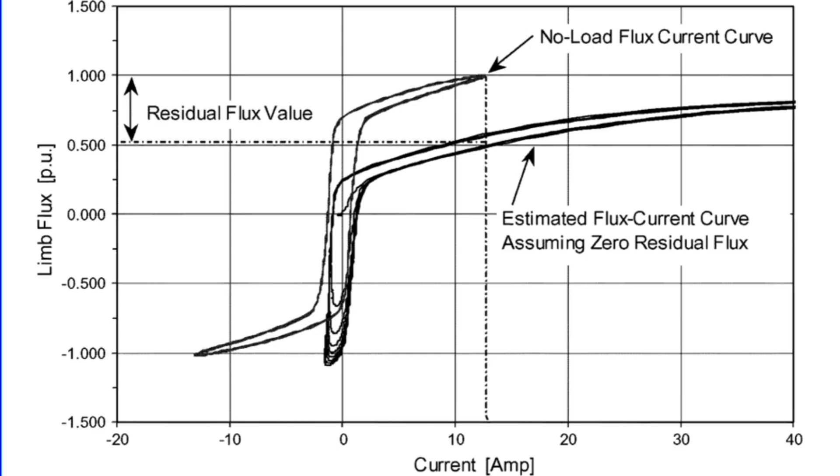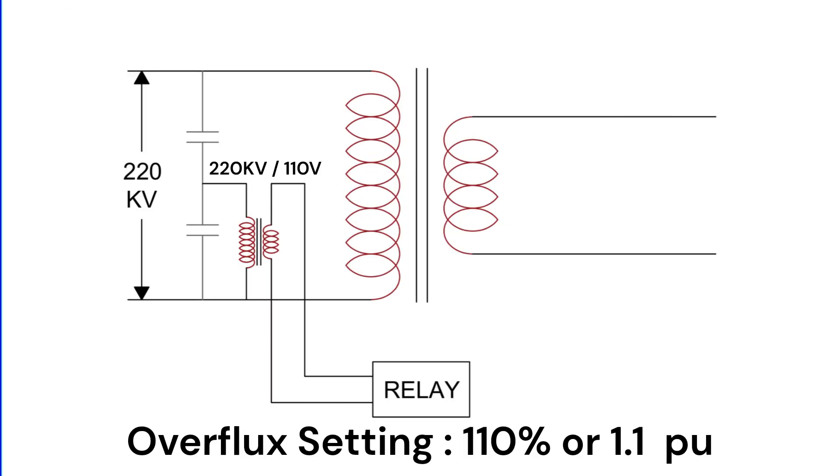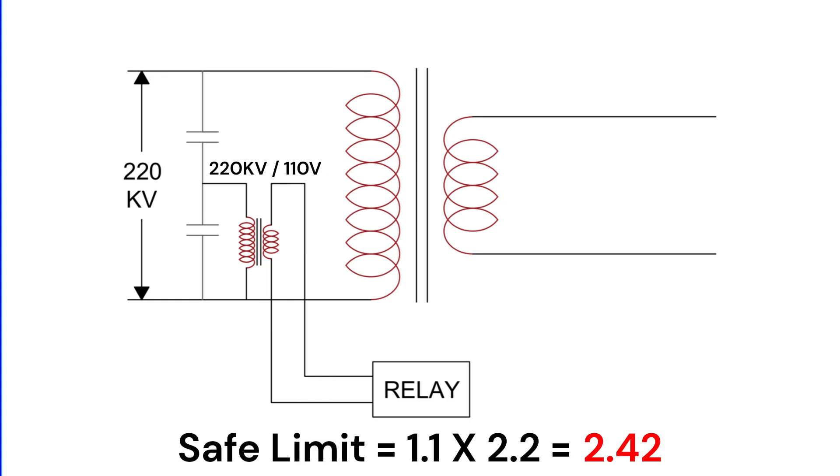To determine the safe operating limit, we look at the hysteresis curve of the core material. Typically, the overflux protection is set at 110% of the nominal value, or 1.1 per unit. So, for our example, the safe limit is 1.1 times 2.2 equals 2.42. If the V over F ratio exceeds 2.42, the transformer core is at risk of overfluxing.